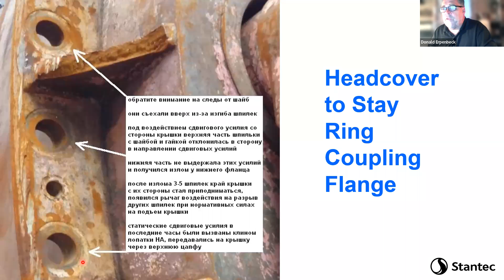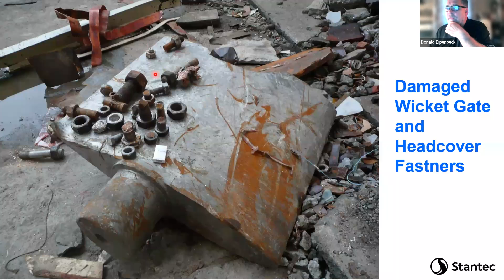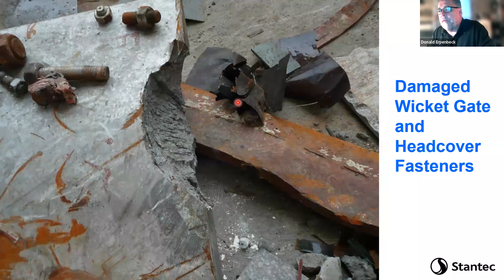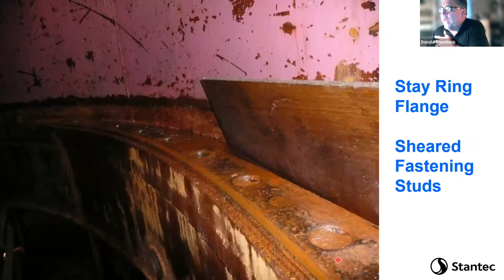So you get a better feel here how big that was, those sheared off pins were. Here's the wicket gate just torn in half. And this is the bottom half of the wicket gate. The top half are still in the head cover here. And here you can see a collection of bolts that really were the main cause of the failure. And so here's that flange that's embedded in the concrete. And if you look here, you see all these sheared bolts still in the hole. And you can see these bolts have failed here.